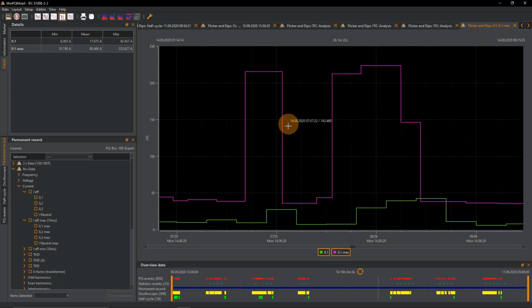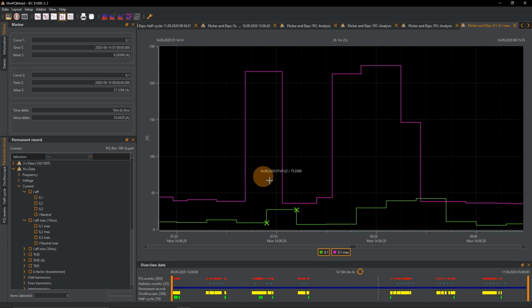So here, for the average value, we see our steps with the markers. I can set marker 1 and 2, and the time delta is 10 minutes. So a 10-minute mean value. Every 10 minutes, we will get a new mean value. But the maximum values are somewhere in between these 10 minutes. So this one, for example, is around the middle, whereas this one is more at the beginning. So the maximum and minimum values always have the exact timestamp. You can see this timestamp in here, for example.